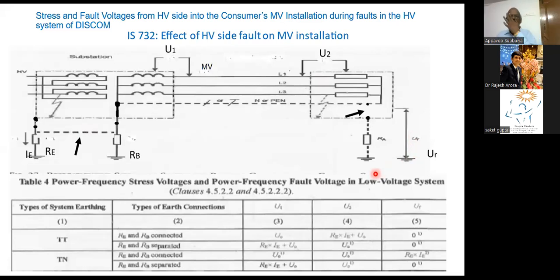So depending upon the earth connection, it will vary. For example, in a TT system, if RE and RB are connected, then you can see the U2 will be, that is, your equipment will fail, but people will be safe. Suppose it is separated, the supplier equipment will be impressed with very high voltage, and we are all safe. In a TNS system, what will be the possibility? If they are interconnected, the touch voltage will be more. If they are separated, you are safe, and the supplier transformer will be, and their person will not be safe. So the thing is, if separated, we are safe. If interconnected, they are safe.